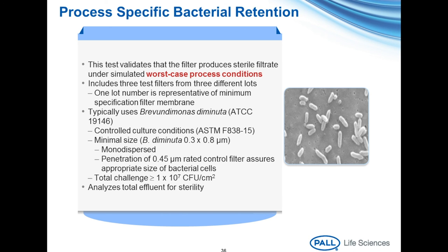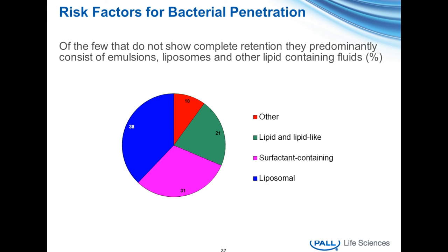In process-specific bacterial retention testing, the filter is tested under a scaled-down version of actual process conditions. It includes three test filters—testing in triplicate—from three different manufacturing lots, and usually must include a minimum specification membrane to cover the entire expanse of manufacturing quality. A 0.45 micron-rated penetration control filter is also tested, documenting the penetrative ability of the test organism. A minimum challenge of 10 to the 7th CFU per centimeter squared is applied, and the entire effluent is passed through a recovery filter. In almost all process-specific filter validations, complete retention is documented. The rare penetration events are predominantly a result of filtration of emulsions, liposomes, or other lipid-containing fluids—which is why it's important to address this risk early in process development.